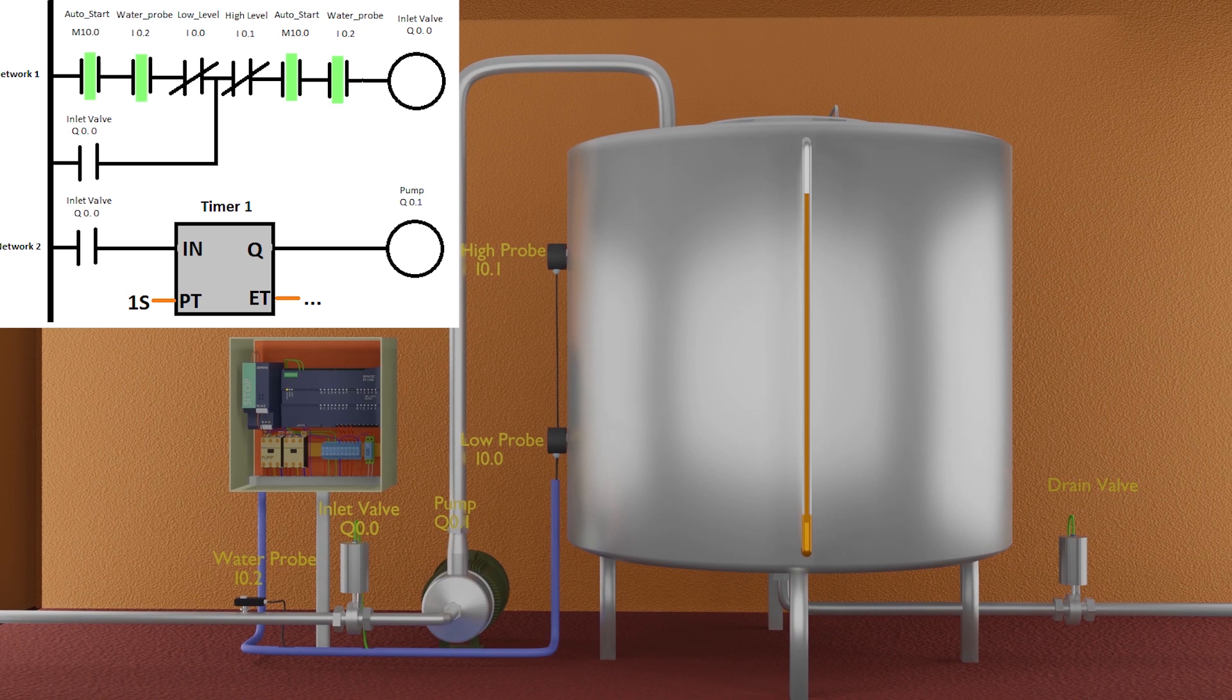Coming back to network 1, if at any time we disable the auto start bit M10.0 or there is no water in the inlet pipe, it will open the contact of water probe I0.2 and it will unlatch and turn off the inlet valve and pump.